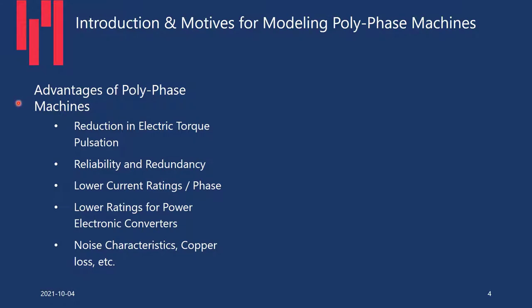What are the advantages of a polyphase machine? First, reduction in electric torque pulsation — the source of torque pulsation is either harmonics from the network or space harmonics from winding distribution, and having more than three phases reduces this pulsation. Second, reliability and redundancy — with more than three phases, you could lose one or two phases and still operate the machine to a reasonable extent. Third, lower current rating per phase and lower ratings for power electronic converters. Additionally, reduced noise characteristics and copper losses.